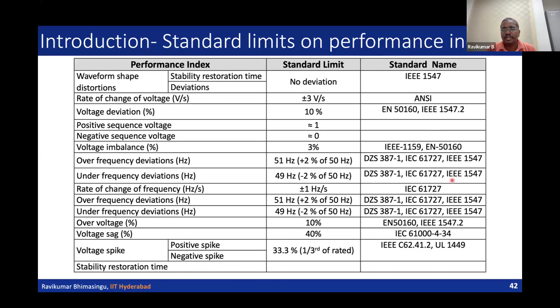Over frequency and under frequency should be plus or minus 2%, and rate of change of frequency plus or minus 1 Hz per second. Over voltage and voltage sag should be 10% and 40% respectively, and if there is a voltage spike, it should be limited to 33%. Stability restoration time should be as fast as possible. These are the standard limits imposed as per the standards displayed here.